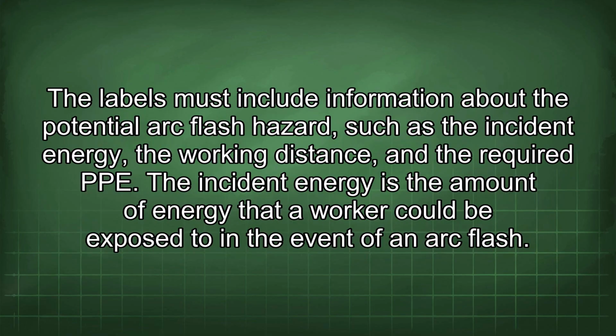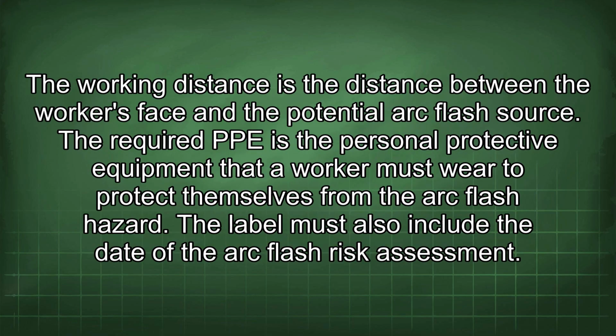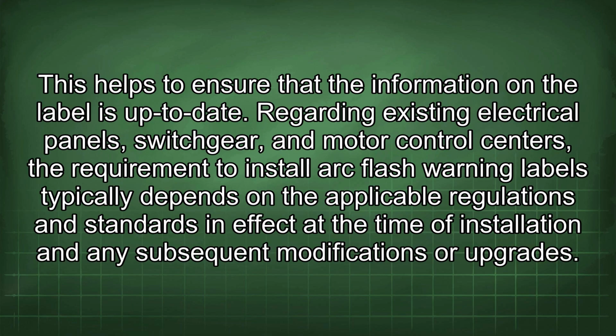The labels must include information about the potential arc flash hazard, such as the incident energy, the working distance, and the required PPE. The incident energy is the amount of energy that a worker could be exposed to in the event of an arc flash. The working distance is the distance between the worker's face and the potential arc flash source. The required PPE is the personal protective equipment that a worker must wear to protect themselves from the arc flash hazard. The label must also include the date of the arc flash risk assessment. This helps to ensure that the information on the label is up to date.